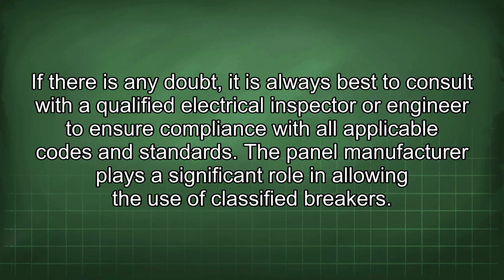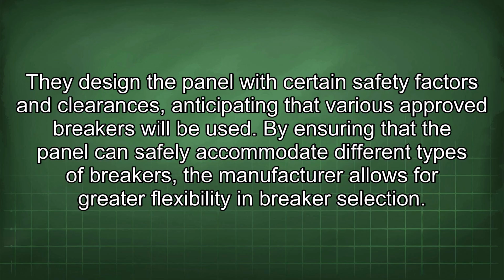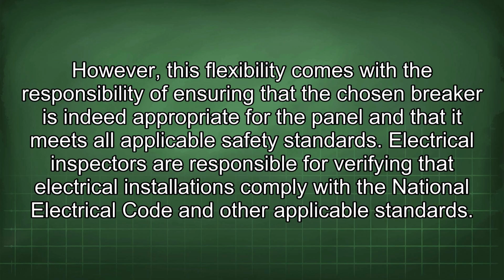The panel manufacturer plays a significant role in allowing the use of classified breakers. They design the panel with certain safety factors and clearances, anticipating that various approved breakers will be used. By ensuring that the panel can safely accommodate different types of breakers, the manufacturer allows for greater flexibility in breaker selection. However, this flexibility comes with the responsibility of ensuring that the chosen breaker is indeed appropriate for the panel and that it meets all applicable safety standards.